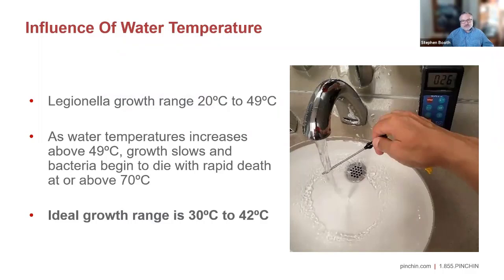There is an influence of water temperature, so how hot you keep your hot water matters a lot. Legionella likes to grow in the 20 to 49 degree Celsius zone. Once water gets to around 49 degrees Celsius, growth slows down, and the bacteria begin to die off very quickly at temperatures above 70 degrees. So we want to keep our hot water above that 50 degree Celsius mark to limit Legionella growth in those systems. The range between 30 and 42 degrees Celsius is really the sweet spot where the bacteria likes to proliferate.